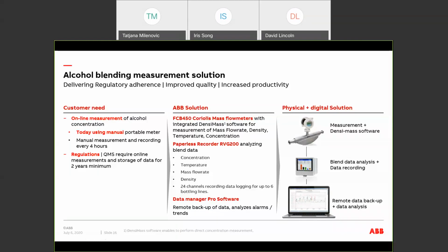From the regulatory side, where they have to keep that information for a minimum of 2 years, we're also able to connect the Coriolis meter using Modbus communications to the paperless digital recorder, our RVG200, and display, log, and record concentration, temperature, mass flow, and density. This device has 24 channels, so it was able to operate up to 6 bottling lines continuously through one recorder.